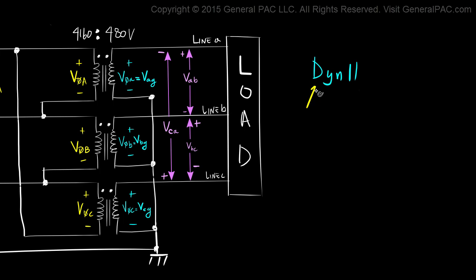The capital D tells us that the high voltage winding is connected in delta. The lower case Y tells us that the low voltage winding is connected in Y or star, same thing.